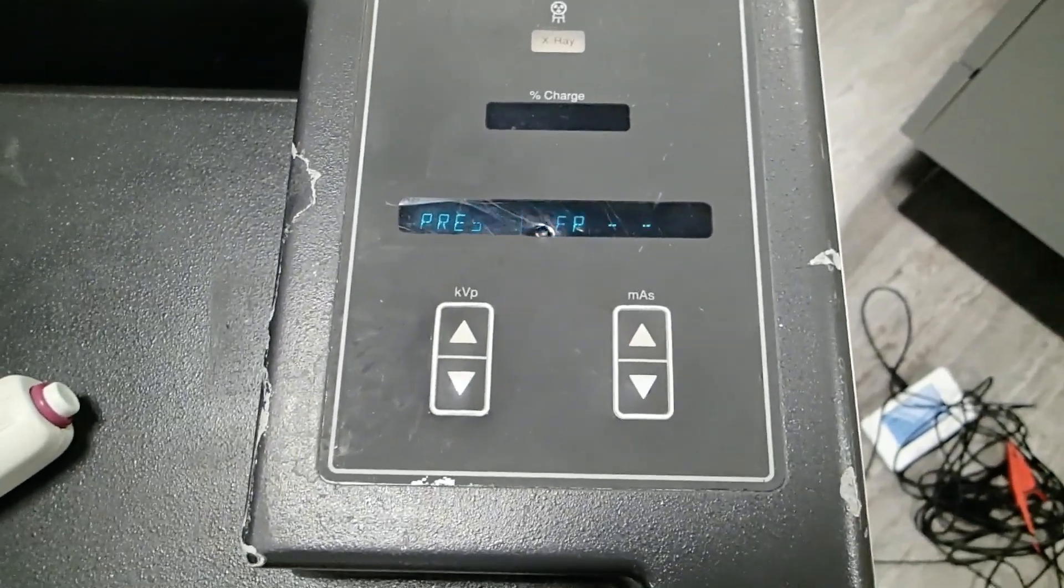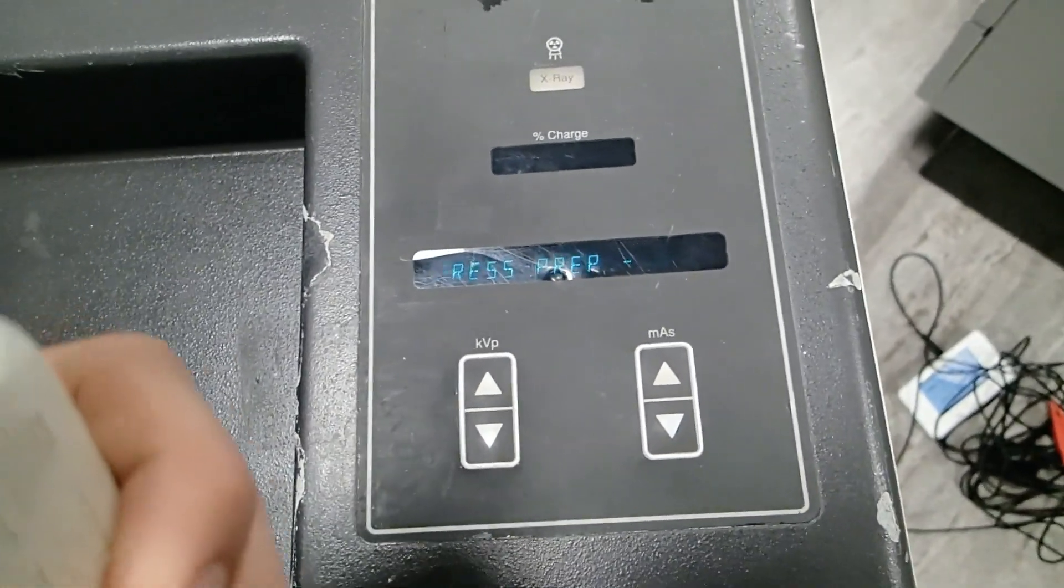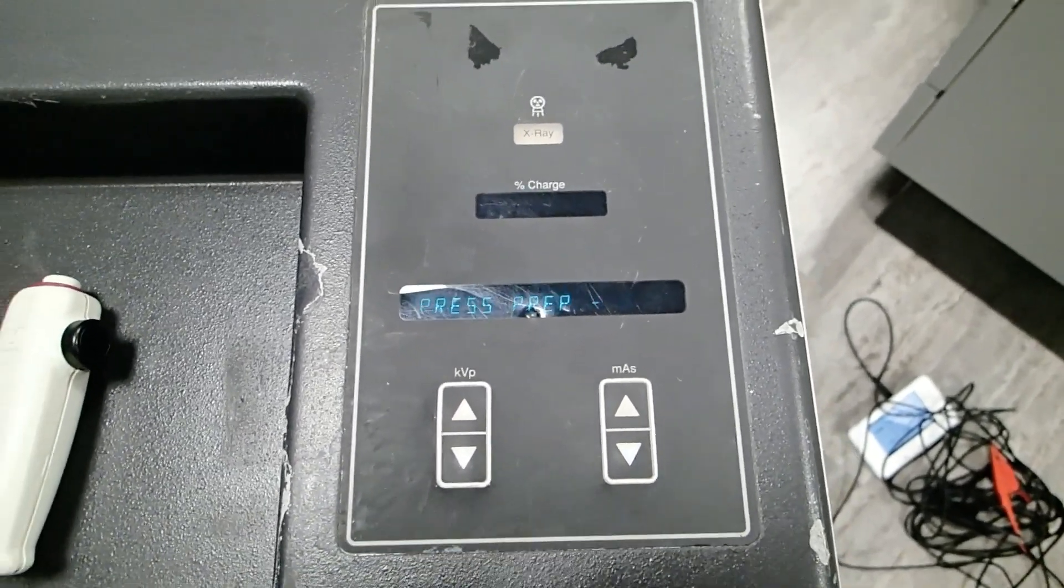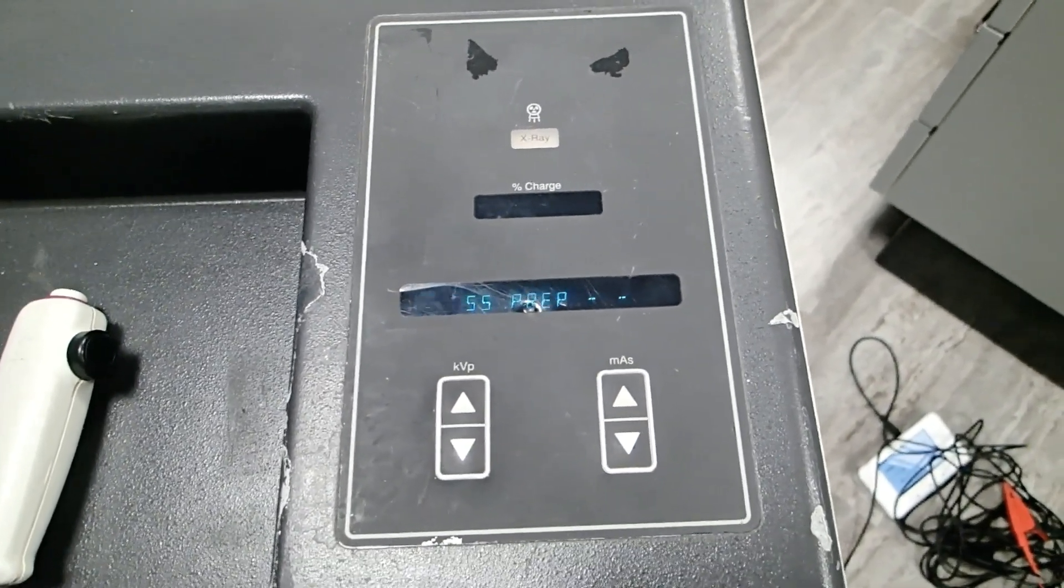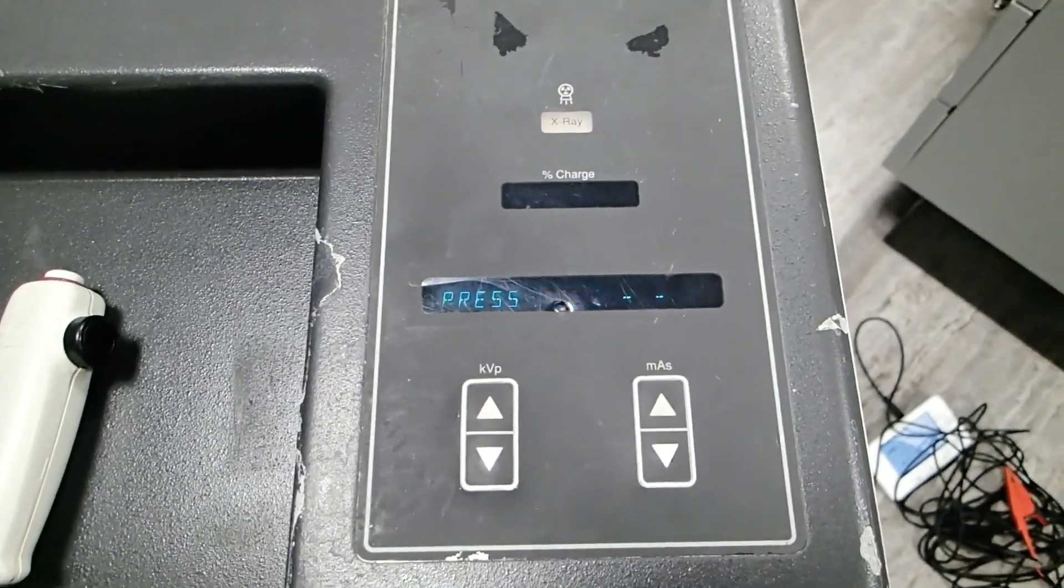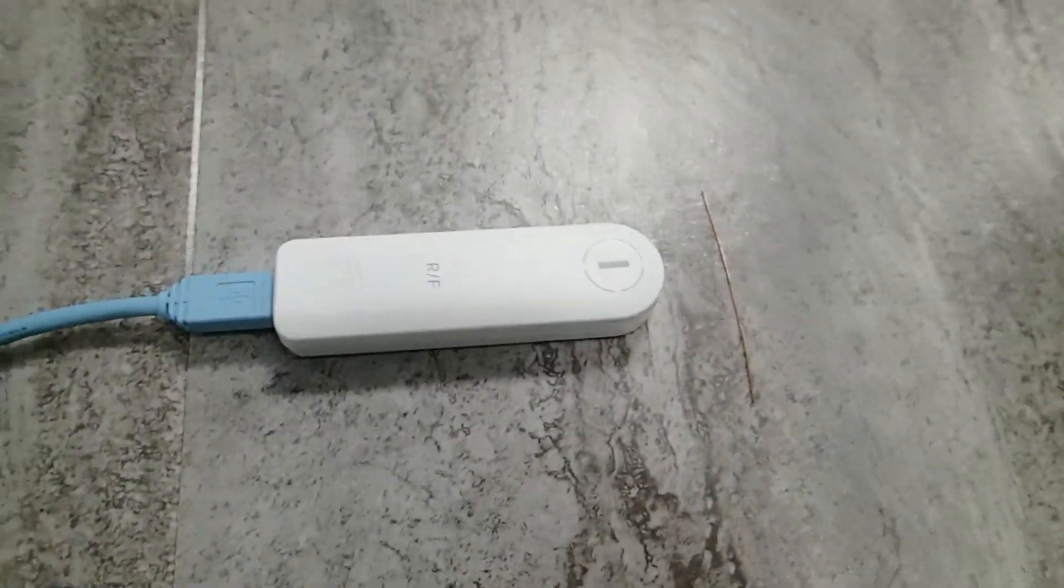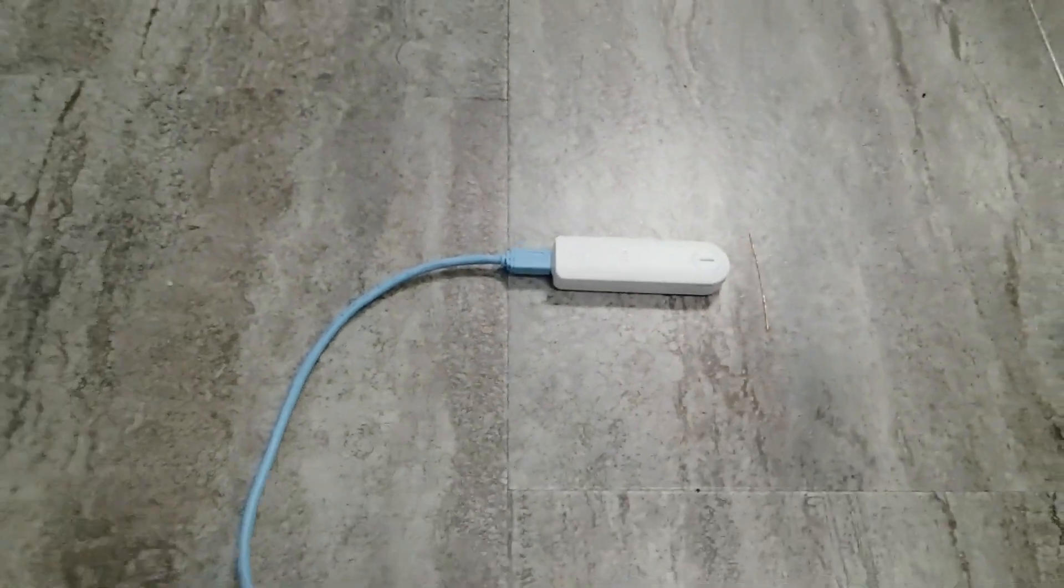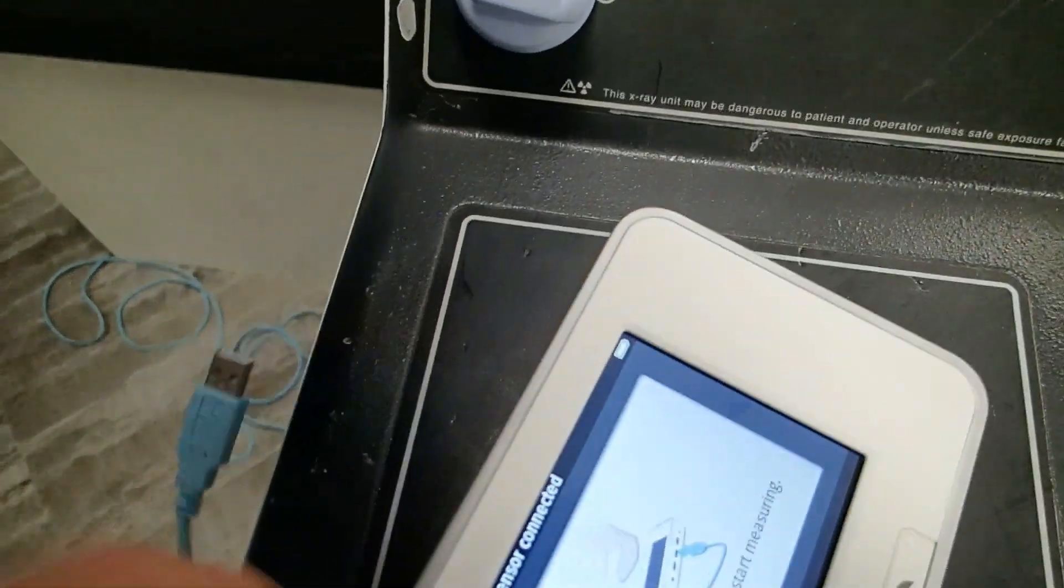Now you're going to hear the x-ray getting ready. Whenever you're going to see press prep, what that means is you're getting ready to press the x-ray and fire the x-rays. You want to make sure that you have a way to measure that KVP that's going to come out of there. We're going to use our RaySafe tester in order to measure the KVP values.